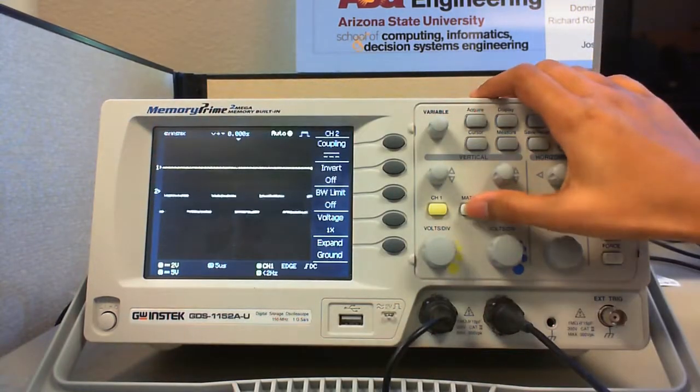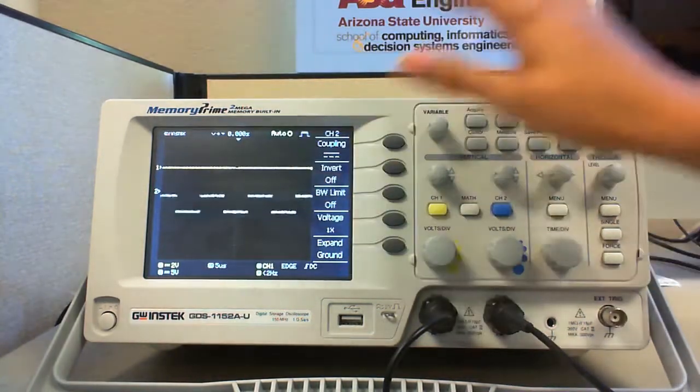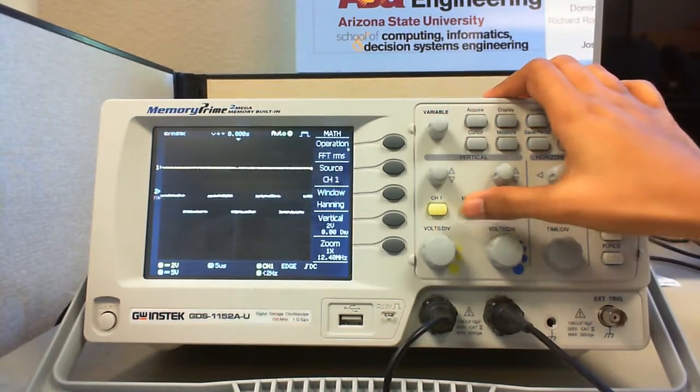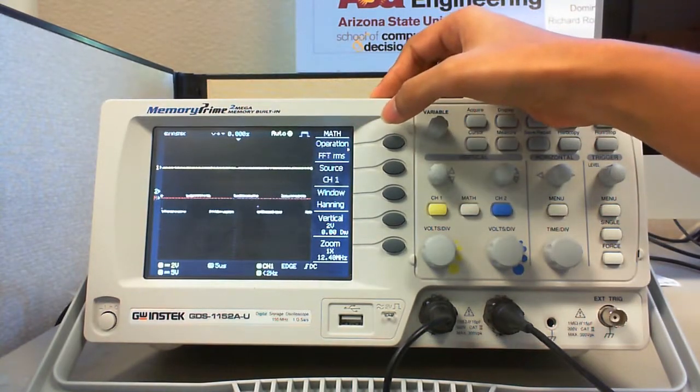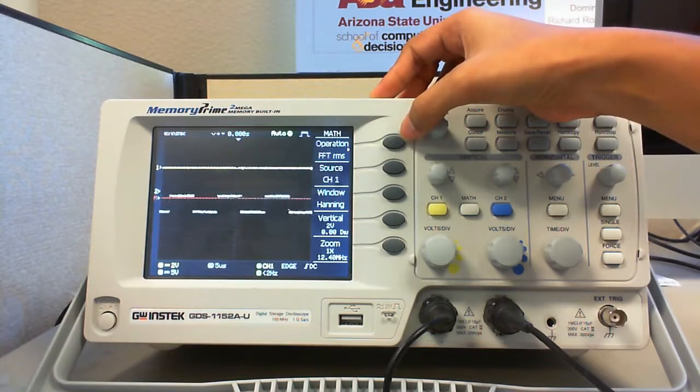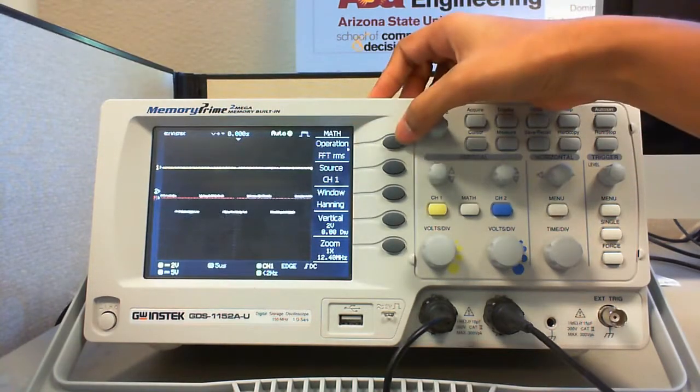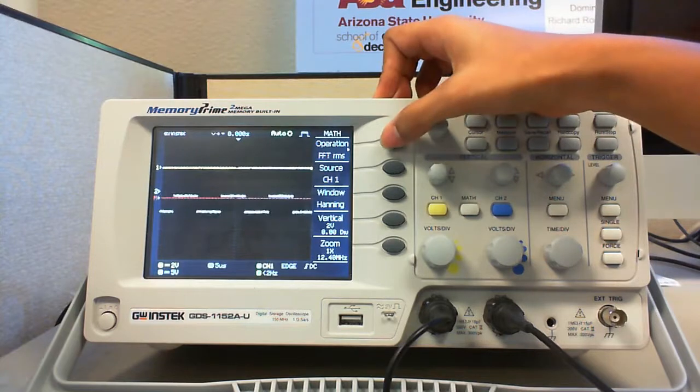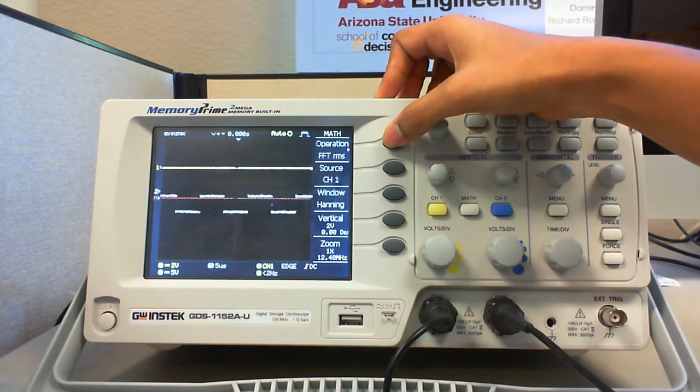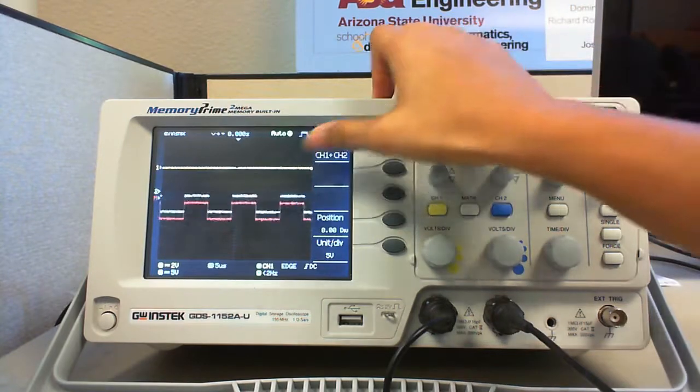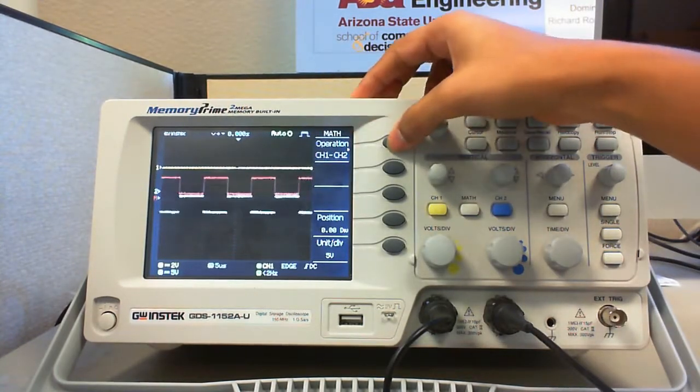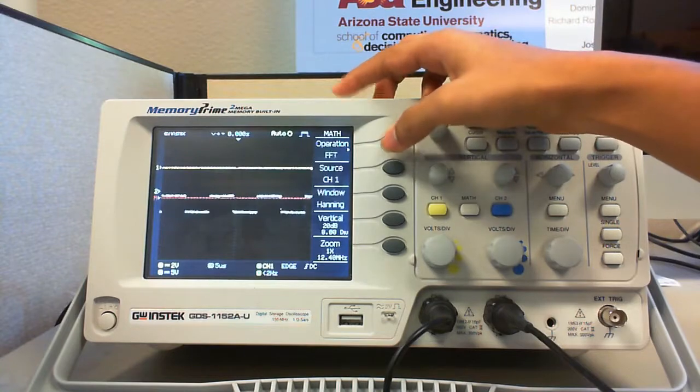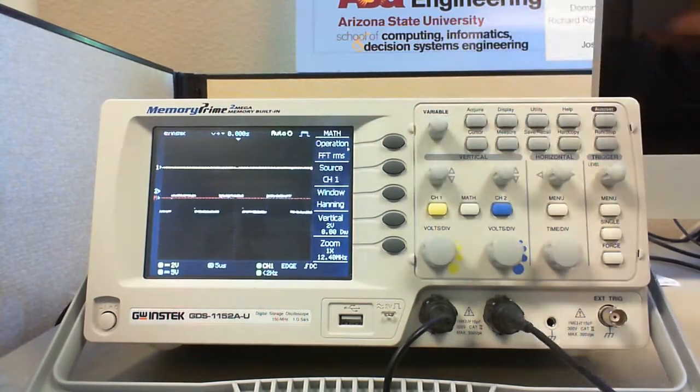Lastly, the math button allows you to perform operations on both the signals of the two channels. You can select the operation of your choice by pressing this button because this points to the first option under the math menu. So, there are many operations under this control knob: addition of two channels, subtraction of two channels, multiplication, fast Fourier transform, and fast Fourier transform RMS.